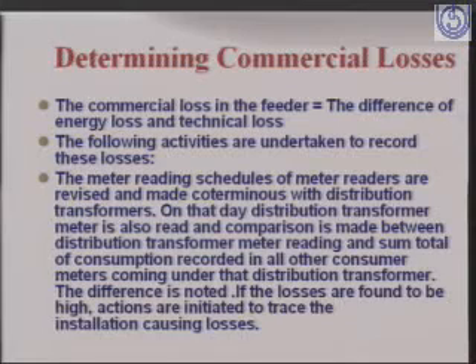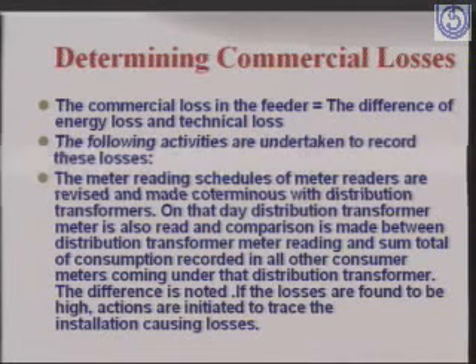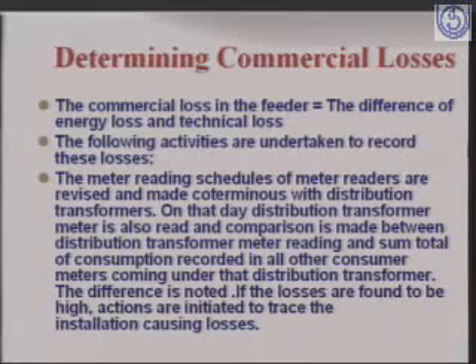So on that day, distribution transformer meter is also read, and comparison is made between distribution transformer meter reading and sum total of consumption recorded in all other consumer meters coming under the distribution transformer. So difference is noted. If the losses are found to be high, actions are initiated to trace the installation causing such losses. So these readings have to be synchronized, that is consumer readings as well as dispatch readings from the transformer side.